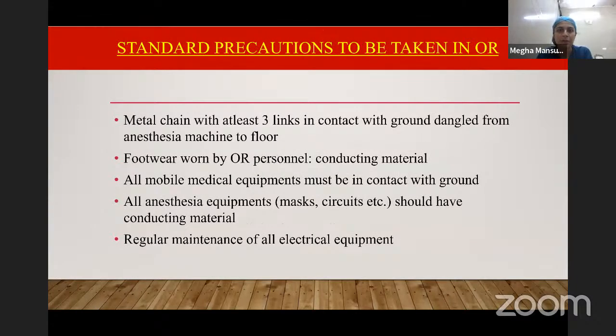There are certain other standard precautions which should be taken in the operating room to minimize current passage to the patient or to the hospital personnel. There should be a metal chain with at least 3 links in contact with the ground dangling from the anesthesia machine to the floor. The footwear worn by operating room personnel should be made of a conducting material. All the mobile medical equipment must be in contact with the ground. All anesthesia equipment such as masks and circuits should have conducting material. We should maintain all our electrical equipment regularly. These steps can minimize electrical hazards in the operating room.